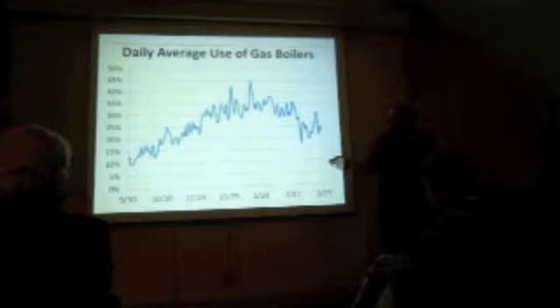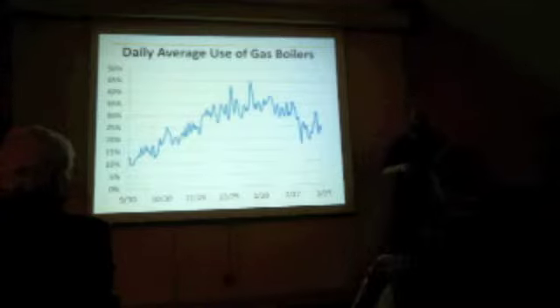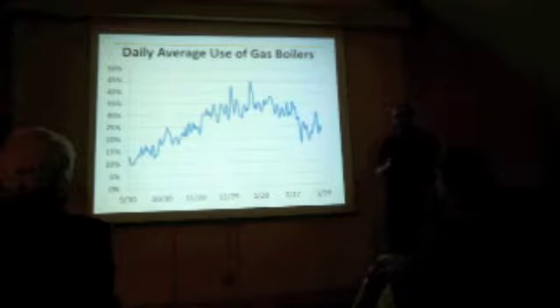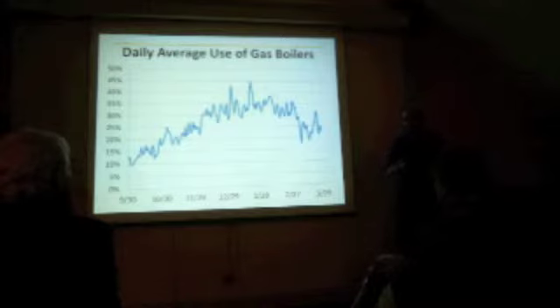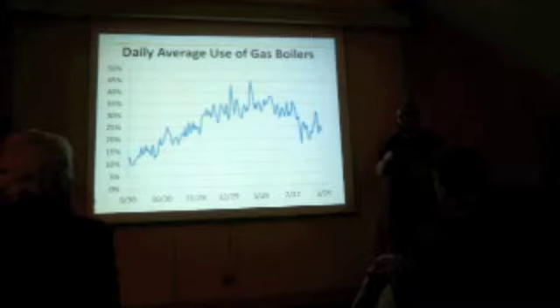What's over here is how much of the capacity of those four boilers you used on average during the day. And so even on your coldest days, over the course of the day, you're not even getting up to half the capacity of those four boilers put together. And that turns out to be not terribly unusual. A factor of 2 overbuilding shows up in a lot of heating systems. And they don't want you to be cold, so just throw another couple units in there, whether or not you need them or what it does to your efficiency.